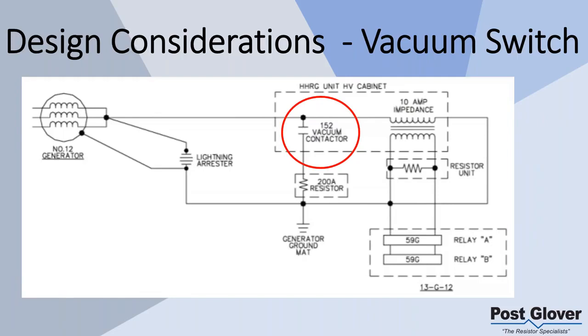In terms of design considerations, one thing I will mention is that a lot of these design considerations are for your single generator with a low resistance ground and high resistance ground in parallel. You're essentially tripping offline a 400 amp resistor, or whatever the resistor is going to be, but a larger resistor, and your currents are changing, and you're going to develop some transient voltages essentially, and you can have some issues with overvoltages.